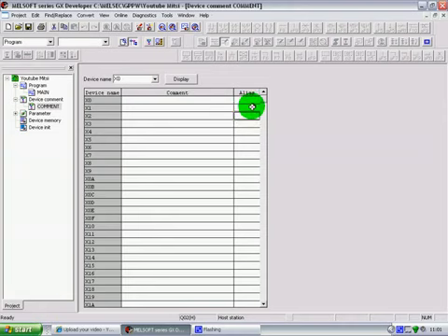You've also got the ability to add an alias in. I tell you what I tend to use these aliases for. Not only do I use the comment to say what it is, so for example, if I've got a plant control system, I might be controlling a valve limit switch. So I might have a valve in the pipeline with a limit switch on the top to tell me whether the valve is opened or closed. What I tend to use for the alias is I will put that limit switch number either off the electrical drawings or off the PID drawings.